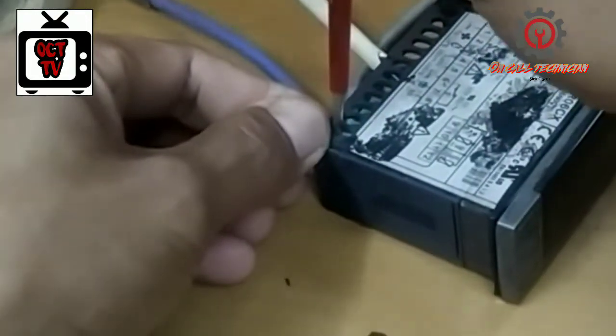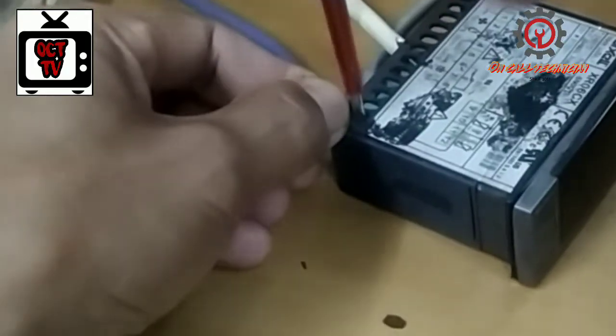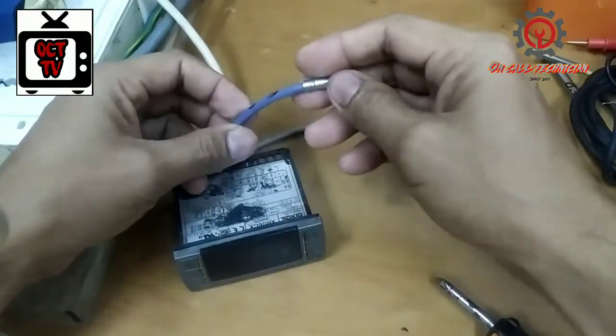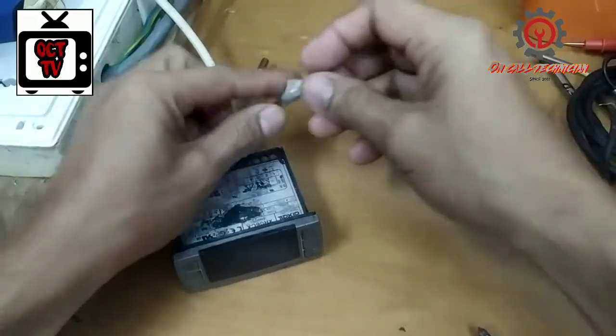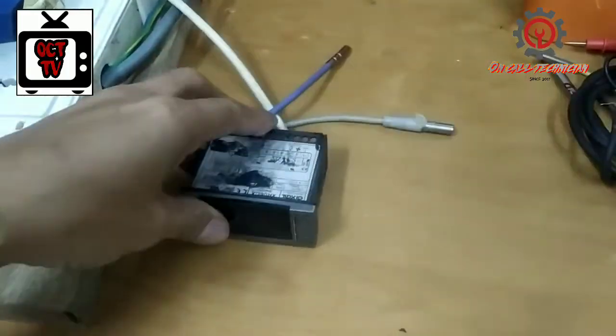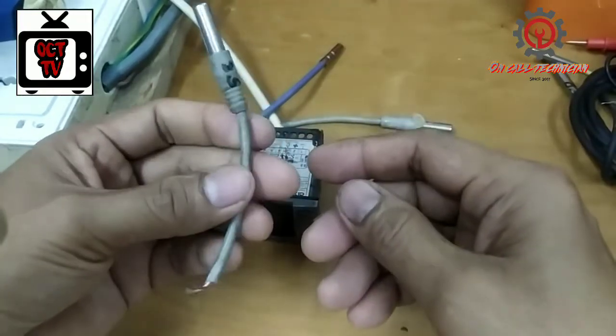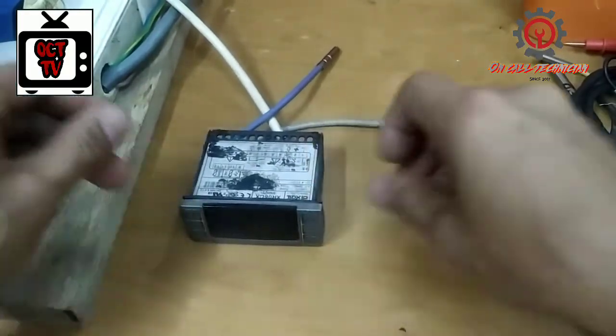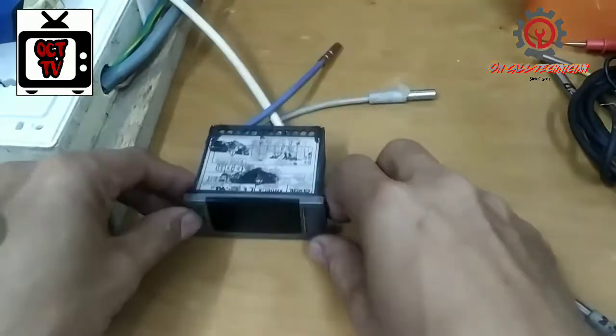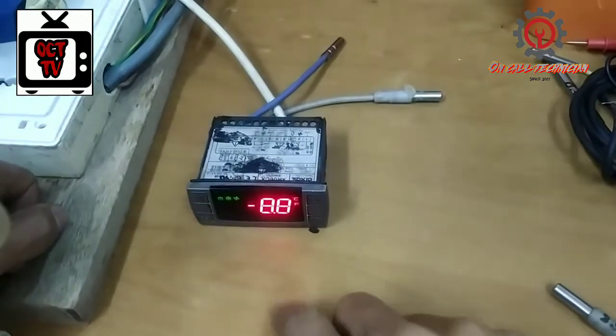Let's see if the P1 alarm is already fixed. This NTC sensor should have a reading of seven to eight kilo ohms. However, the faulty sensor's value has changed — it now reads only around 2-point-something kilo ohms. So let's power it on and see if the issue is resolved.